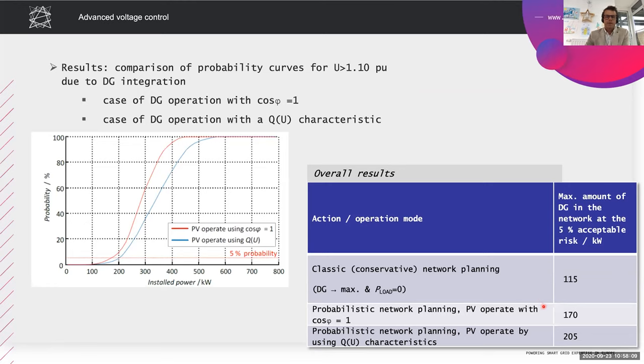If you use the probabilistic approach, this means that you take into account that not all the distributed generators generate the maximum power at the same time. You take into account that there is always some load, based on the data, and that it never happens that the load is zero and so on. You can increase this hosting capacity to 170 kilowatts. So basically this comes for free. You just changed the methodology. You did not make any investments in the network. If you further assume that the distributed generators contribute to voltage control by means of reactive power control, you can increase this amount of installed DG to 205 kilowatts. So as you can see, different approaches enable us to increase the hosting capacity without the need to reinforce the network. And that is the main message.